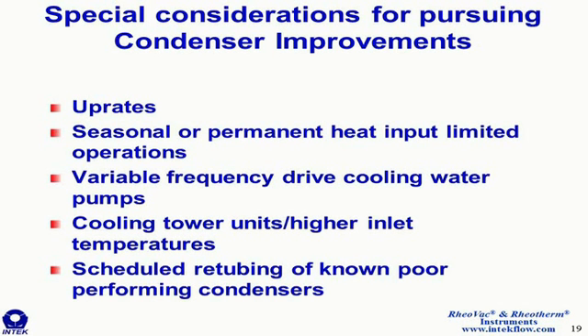When taking a look at any condenser upgrade project, there are some special considerations for pursuing one of these projects that provide additional economic incentive. If the unit is going through an upgrade where more steam is being put into the condenser than it was originally designed for, then a condenser retrofit or upgrade might be able to offset that pressure increase.